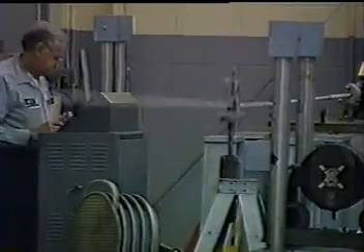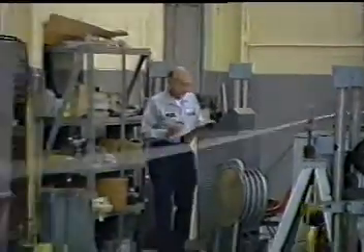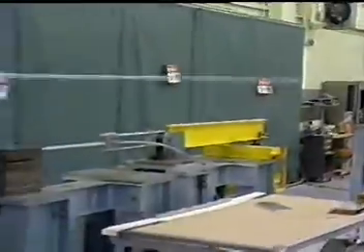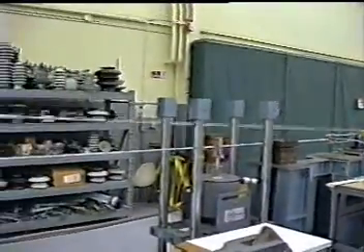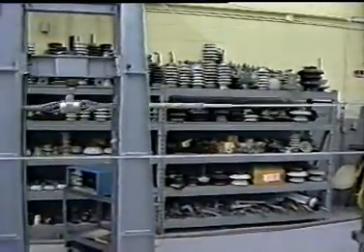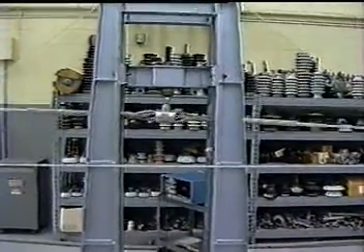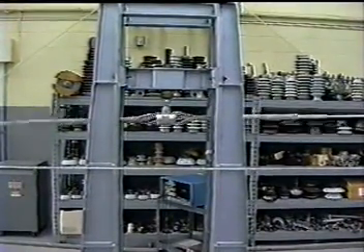End and look at the suspension point. We have very long loop lengths. This actual span is approximately 25 meters in loop length. The amplitude of galloping motion is approximately 1 meter.